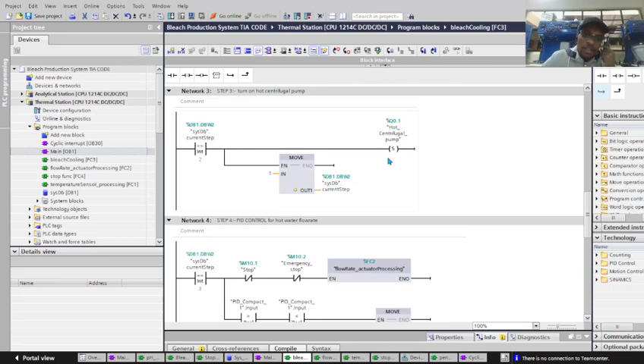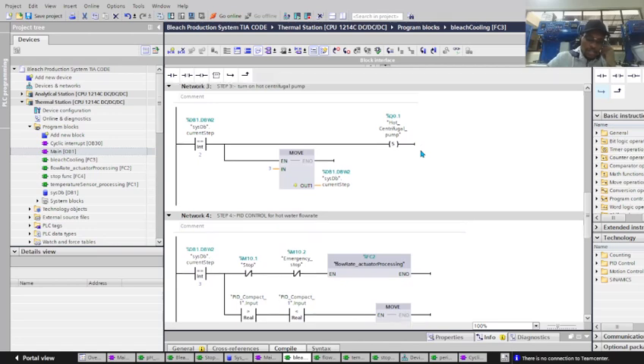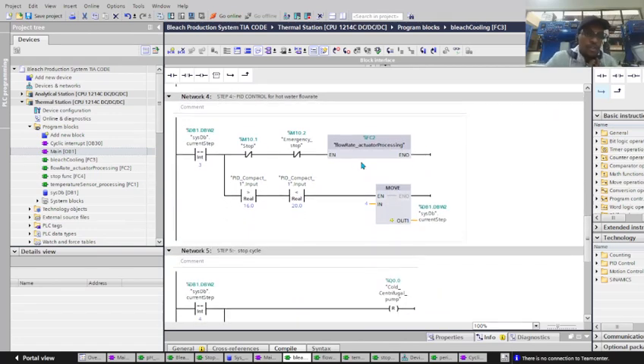We then start the hot water centrifugal pump to pump the hot water through its own hot water system, and then we control the temperature of the process fluid. We have a PID here, and we are controlling the flow rate of the hot water. So once the chiller has cooled the process water to below 16, the PID will start the flow of the hot water to the hot water heat exchanger to warm it up a bit and ensure that it remains within the range.